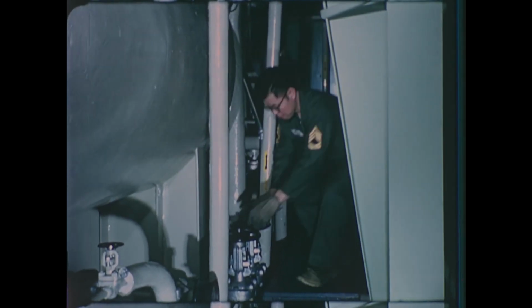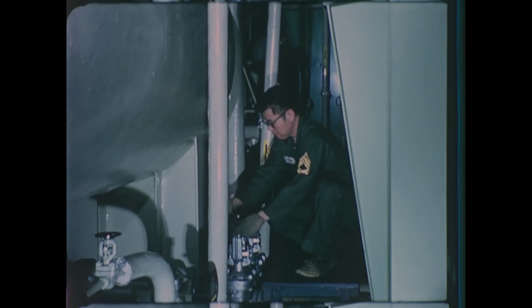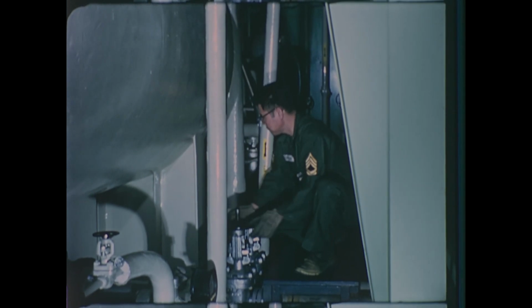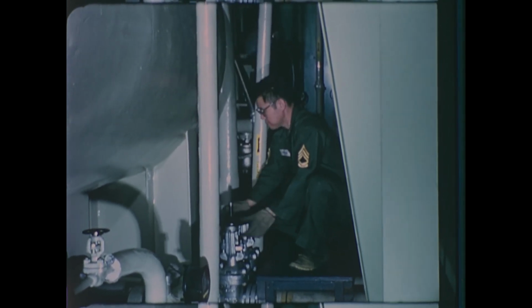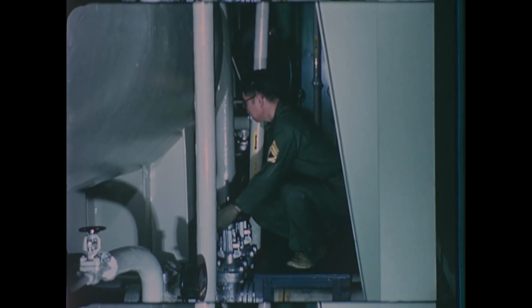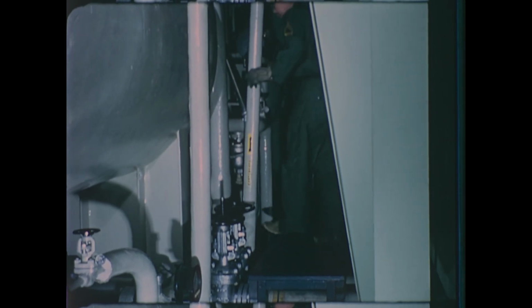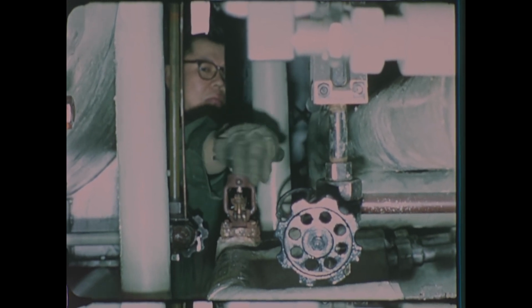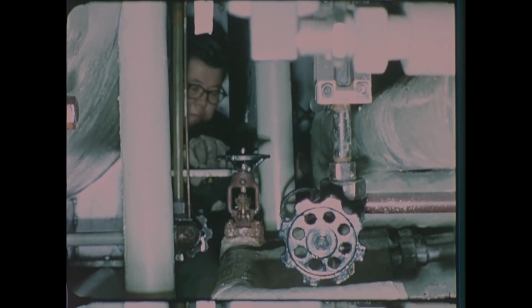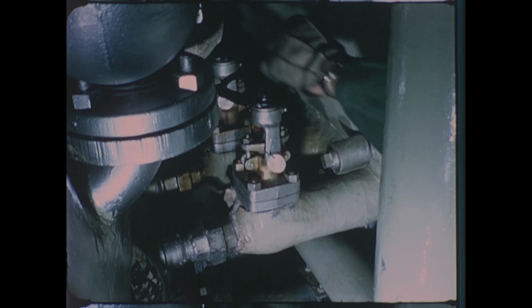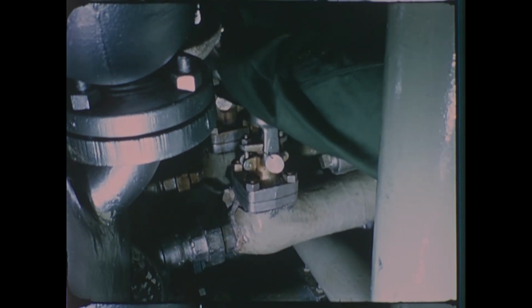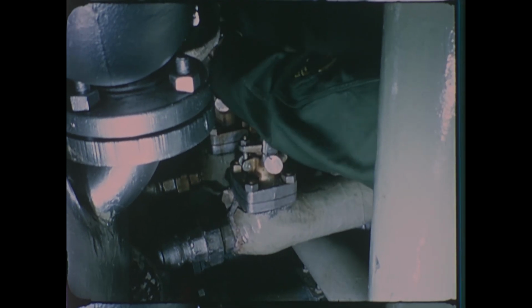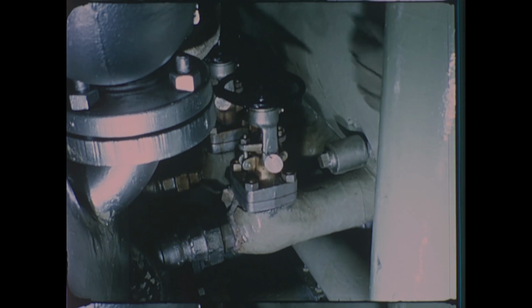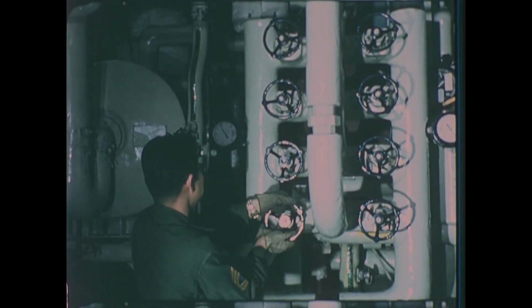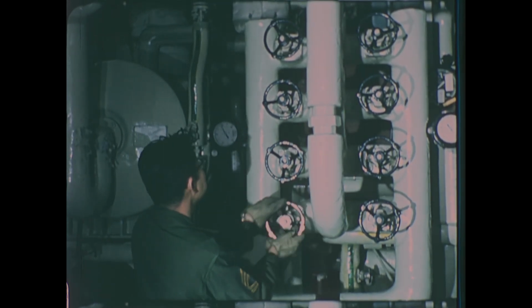Selecting either of the two air ejectors, the operator opens the valve to discharge overboard. Opening the valve on the auxiliary steam supply to feed steam to the first stage of the air ejector. Opening another steam line valve to place the air ejector second stage in service. Now the operator opens the valve from the air offtake line header to the desired condenser and allows the ejector to evacuate the offtake line.